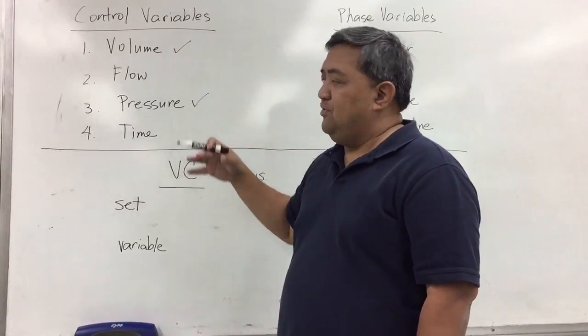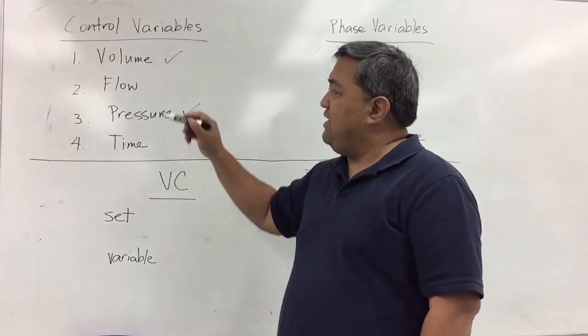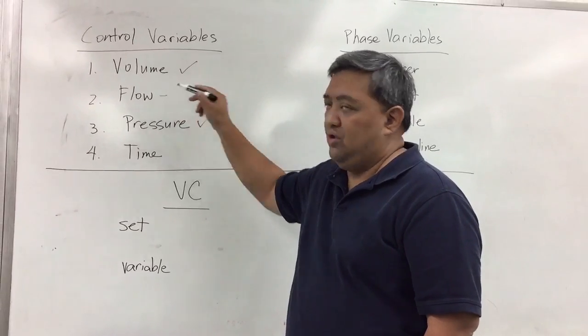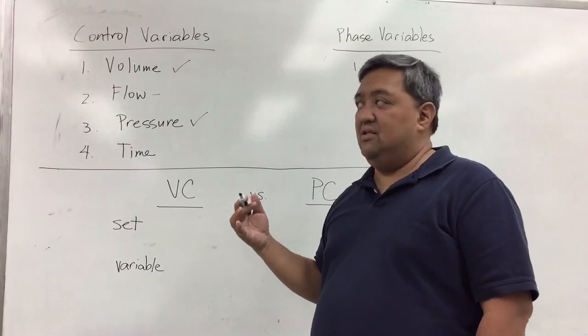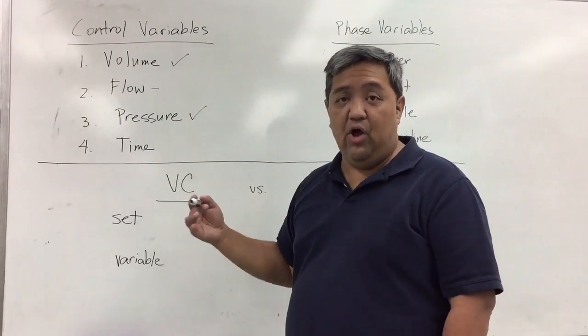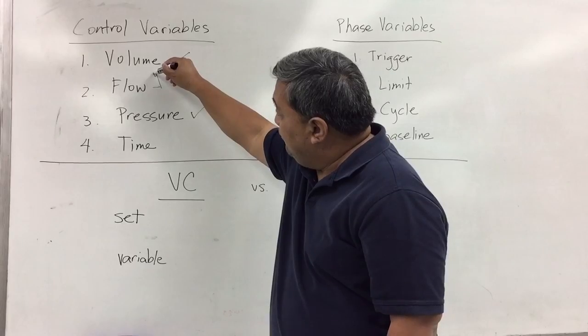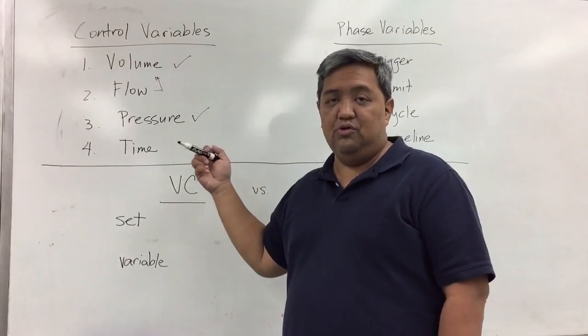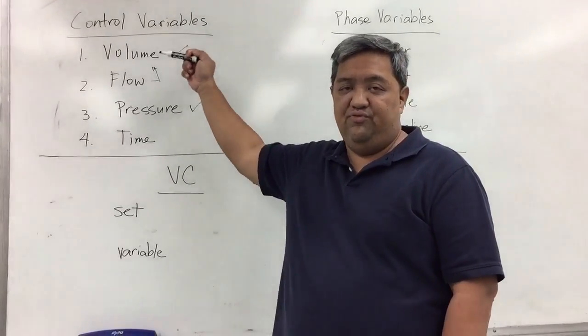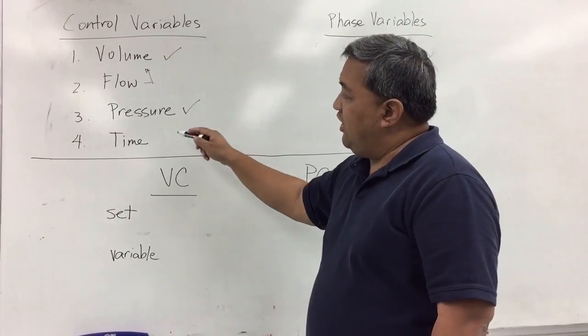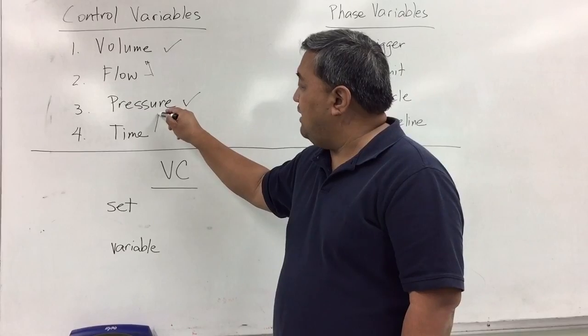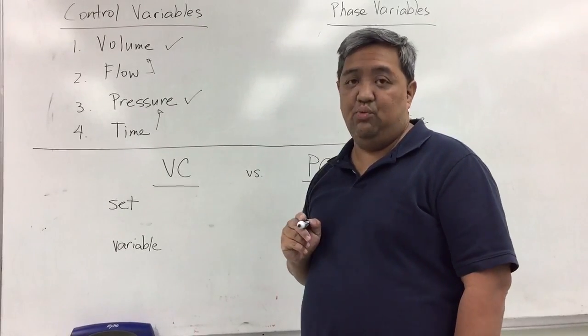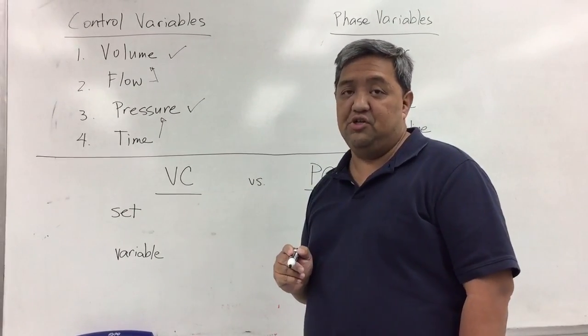A control variable usually is set. That means that if you have a flow controller, your flow is set and the control variable that has a set flow is basically volume control. So flow controller is usually associated with volume control. On the other hand, the time controller, since it is a set time, is usually associated with your pressure controller.